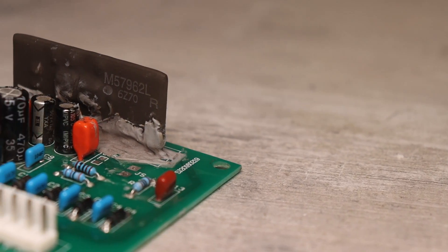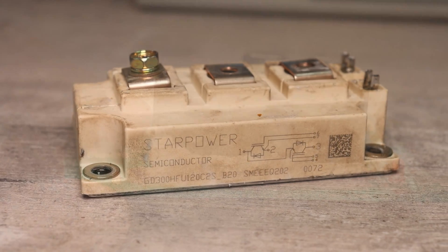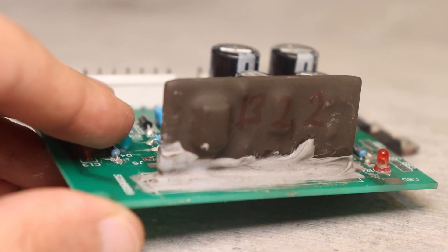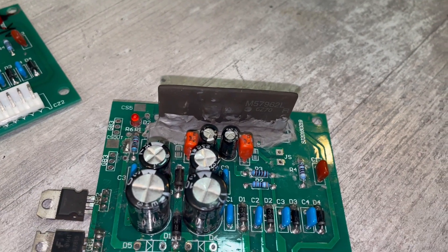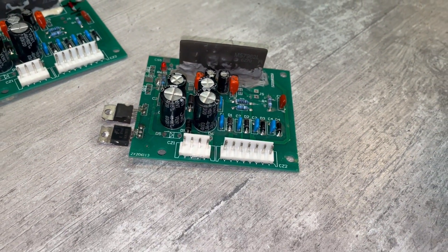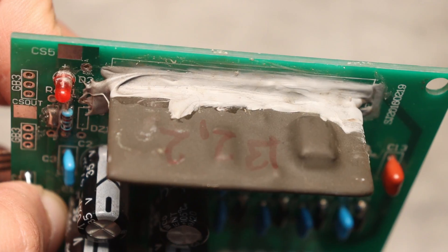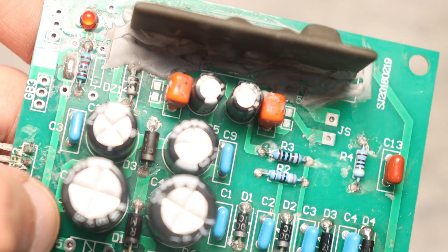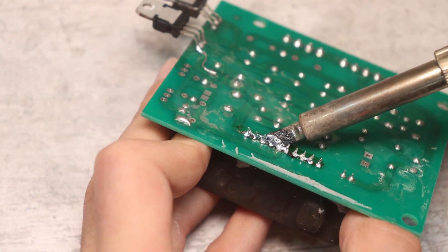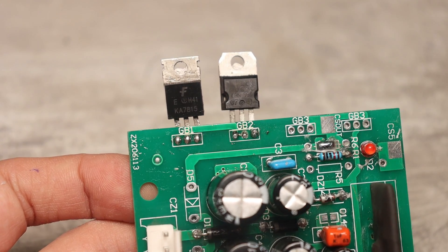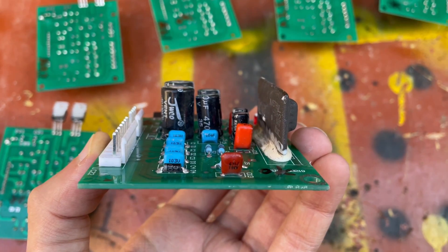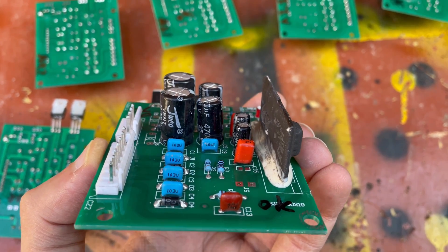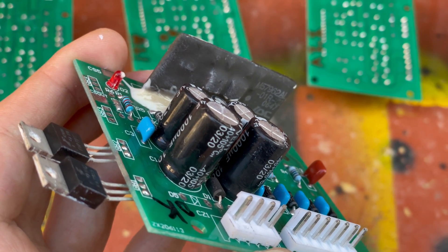One of the drivers was repaired using a component that isn't recommended for these modules. In addition, the repairman covered the driver pins with sealant. I think this is an ordinary sealant from a construction store, but for our case such a sealant cannot be used because almost all conventional sealants are acid-based. As a result, I changed the micro assembly and put the board in order. Plus 15V and minus 12V stabilizers were normal. I just renewed solder and that's all. All 8 drivers have been serviced and tested.